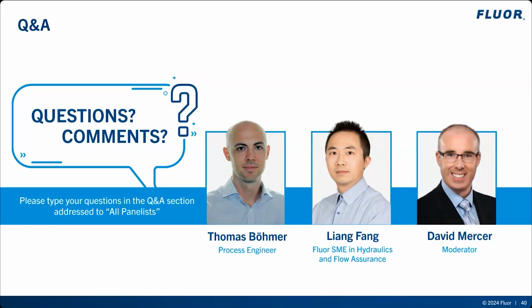And your second question relates to vacuum conditions. Vacuum is a very tricky question, and I don't think any of the available commercial software can accurately predict it. We have some models available across different software, but I have to say none of them can produce accurate results, because vacuum and column separation is a three-dimensional phenomenon rather than two-dimensional. We need to carefully analyze and adjust those parameters based on engineering experience.